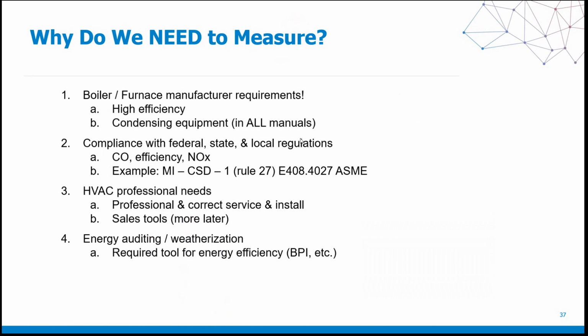It's going to help you comply with the federal, state, and local regulations when it comes to carbon monoxide, efficiency, and NOx. For the HVAC professional, you can use it as a sales tool, which I'll go over in a second. But it's also, again, the professional and correct way to conduct yourself on a service call. Anytime you touch a fuel-fired piece of equipment, you should be doing a combustion test so that you know what the baseline performance level is of that equipment.